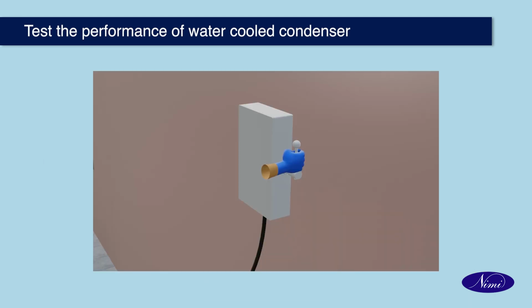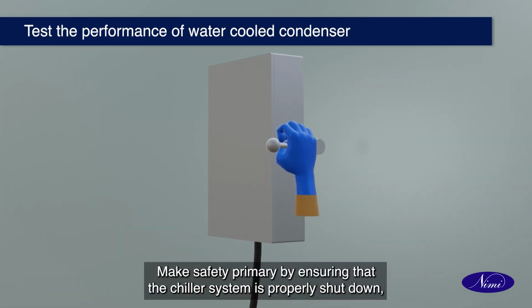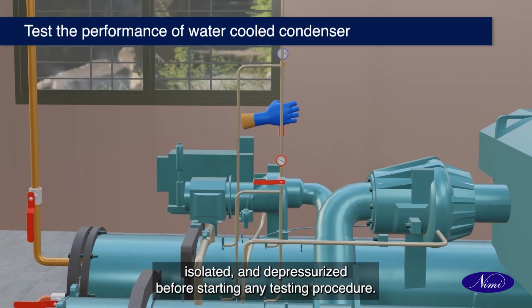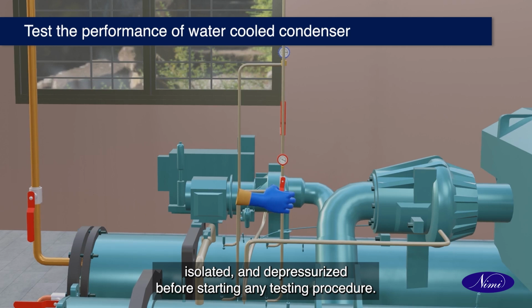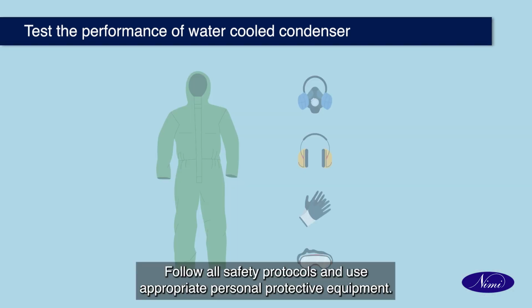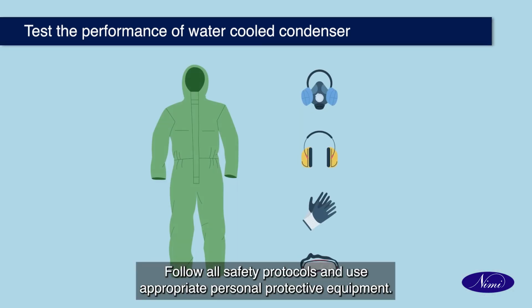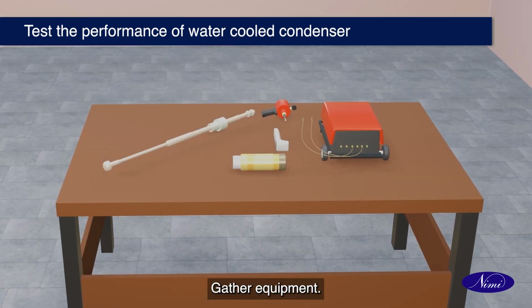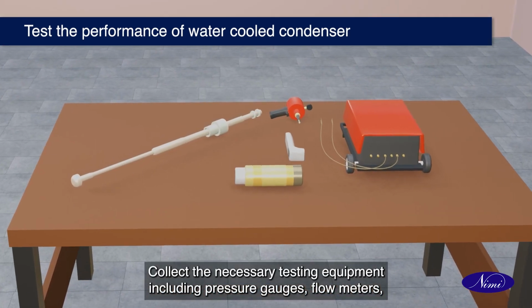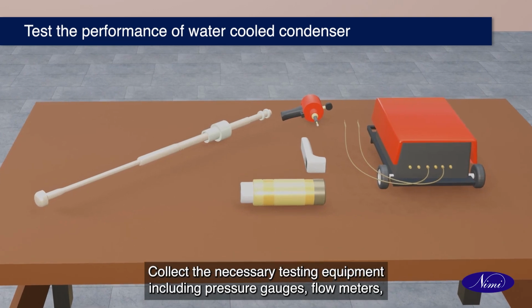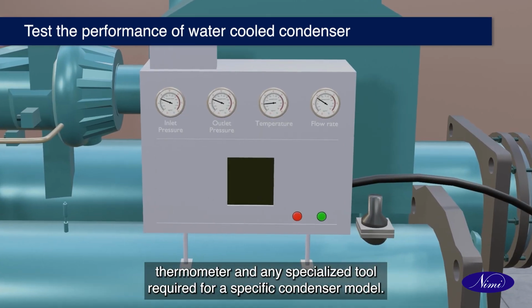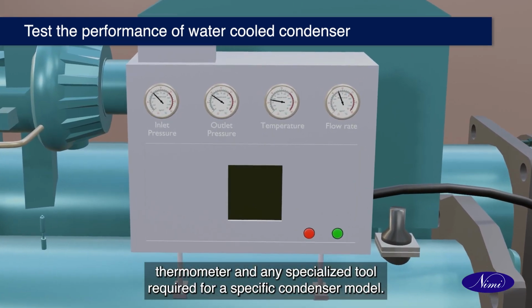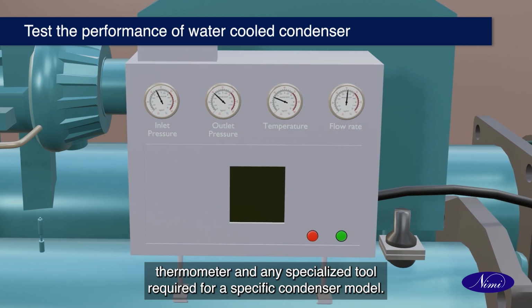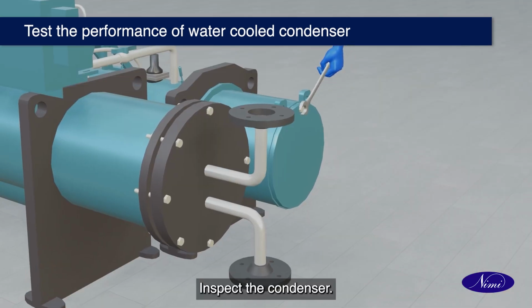Safety precautions. Make safety primary by ensuring that the chiller system is properly shut down, isolated, and depressurized before starting any testing procedure. Follow all safety protocols and use appropriate personal protective equipment. Gather equipment. Collect the necessary testing equipment, including pressure gauges, flow meters, thermometer, and any specialized tool required for a specific condenser model.